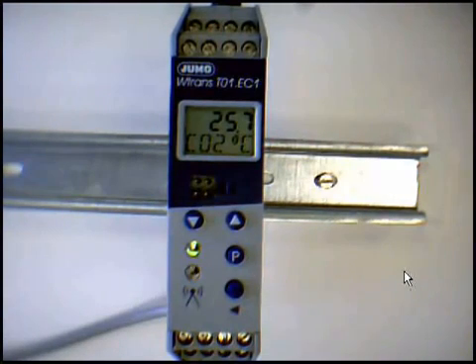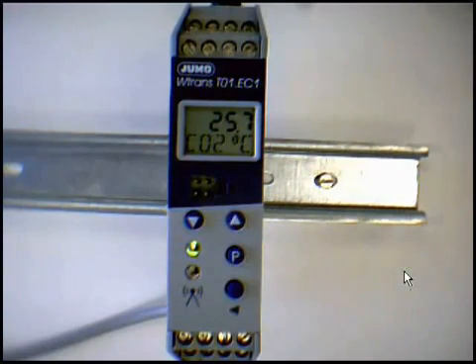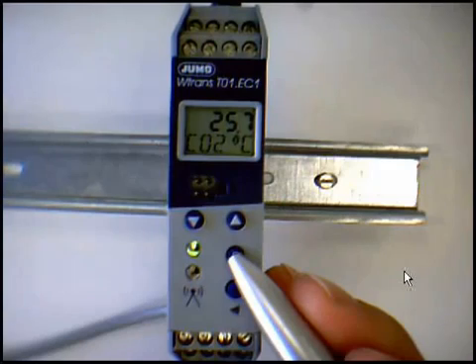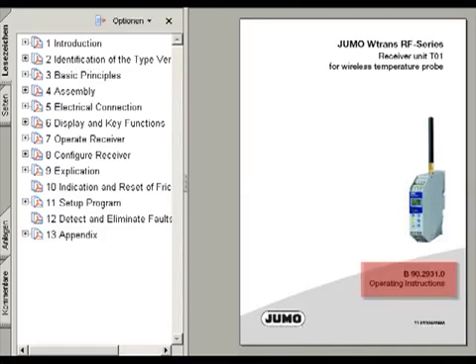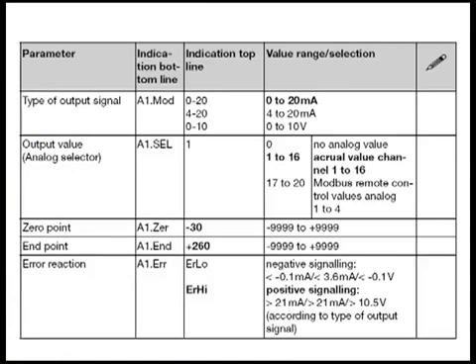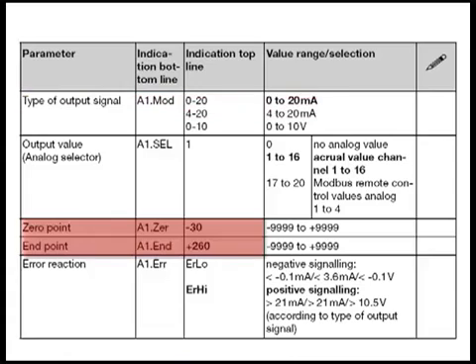Further configuration steps are realized in the parameter level. We reach the parameter level by pressing the P key for at least 2 seconds. Factory made, the analog outputs 1 and 2 provide the measuring values of the channels 1 and 2. Output is made as standard signal 0 to 20 milliamps, which corresponds to a temperature of minus 30 to 260 centigrades.